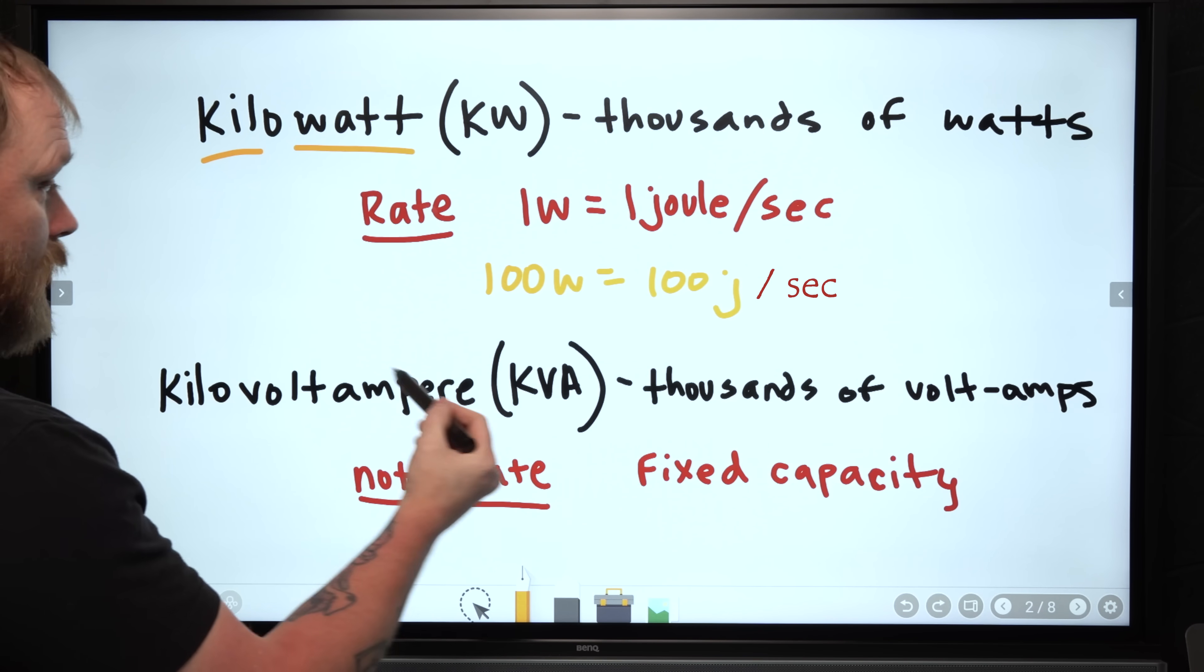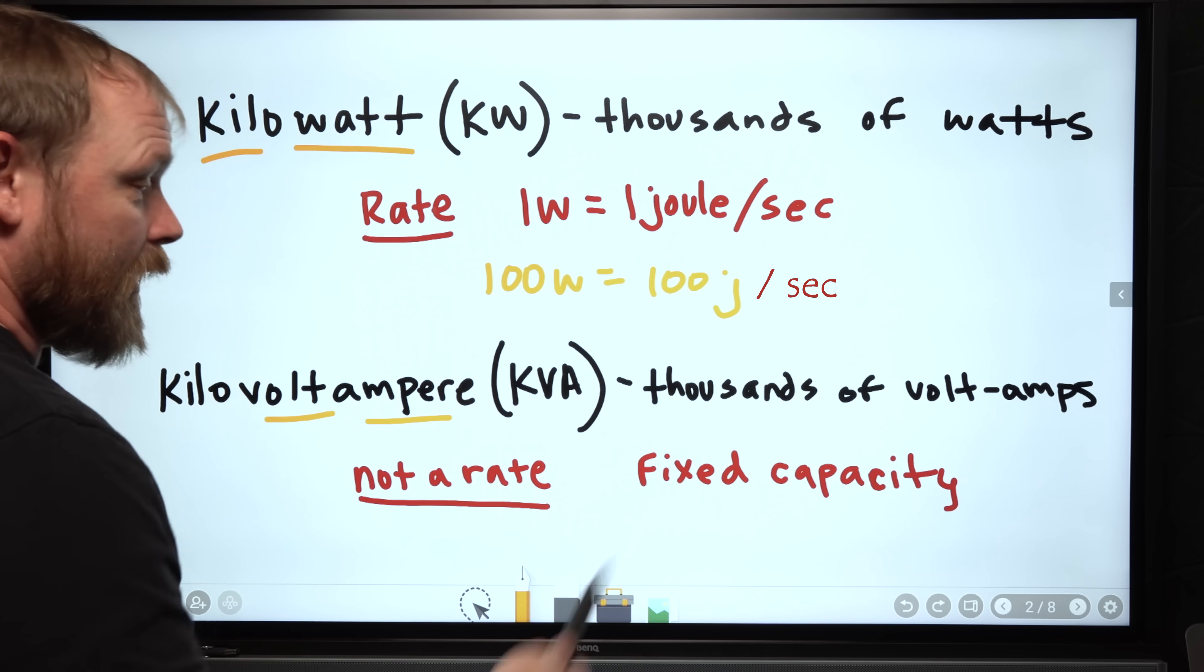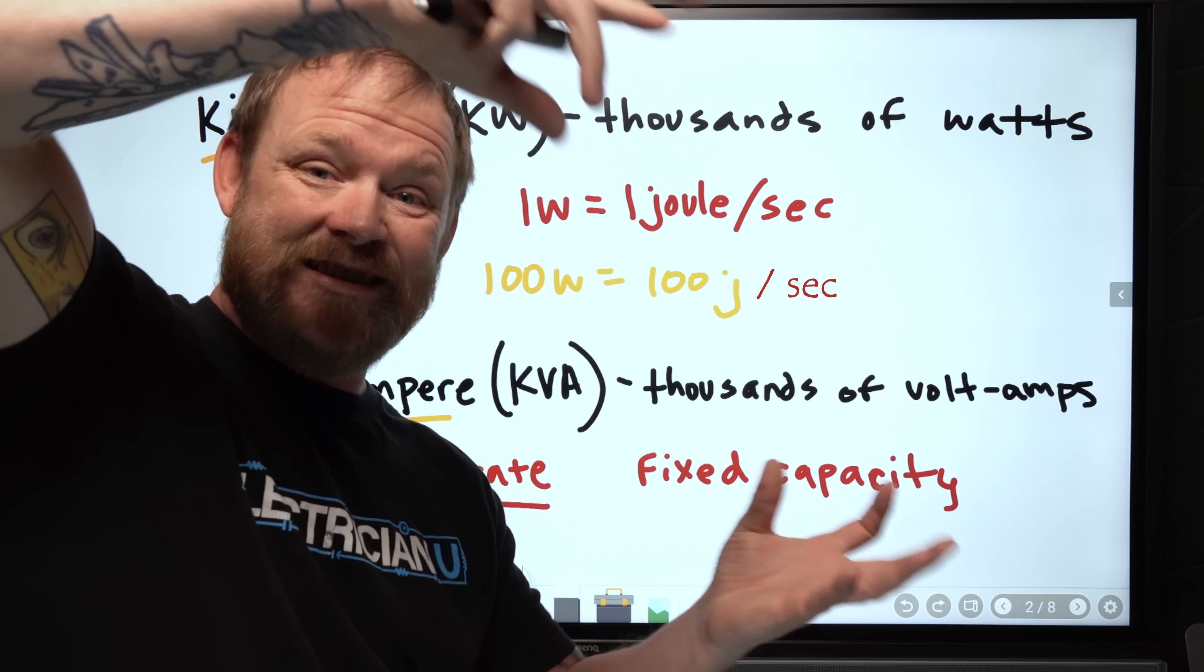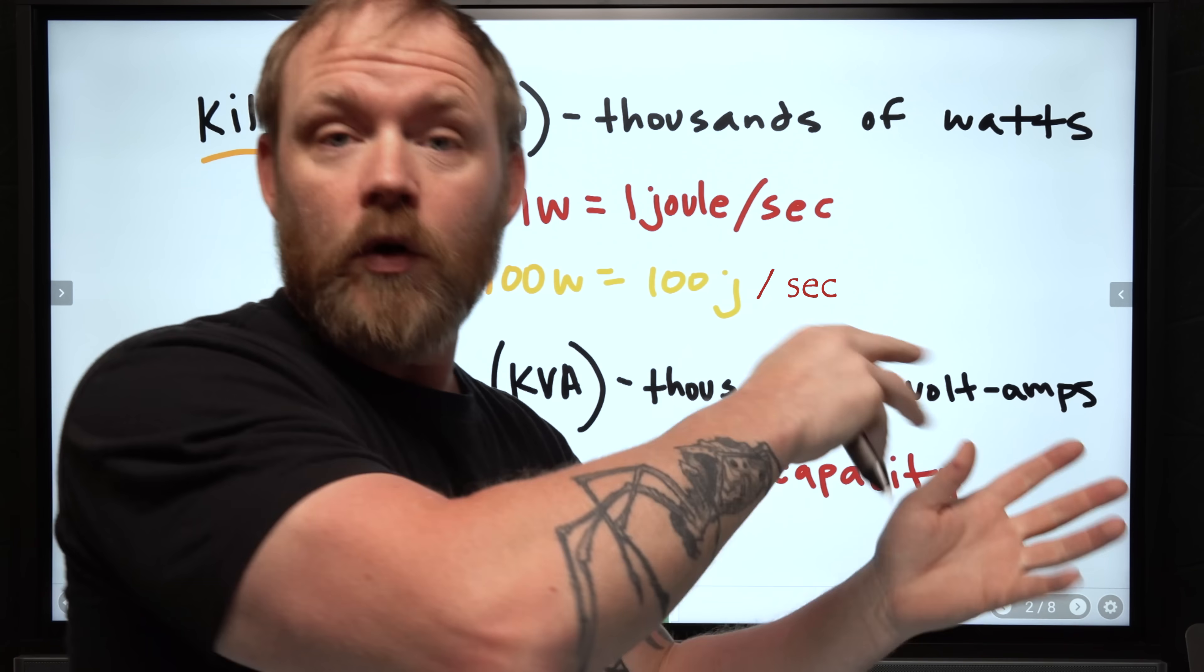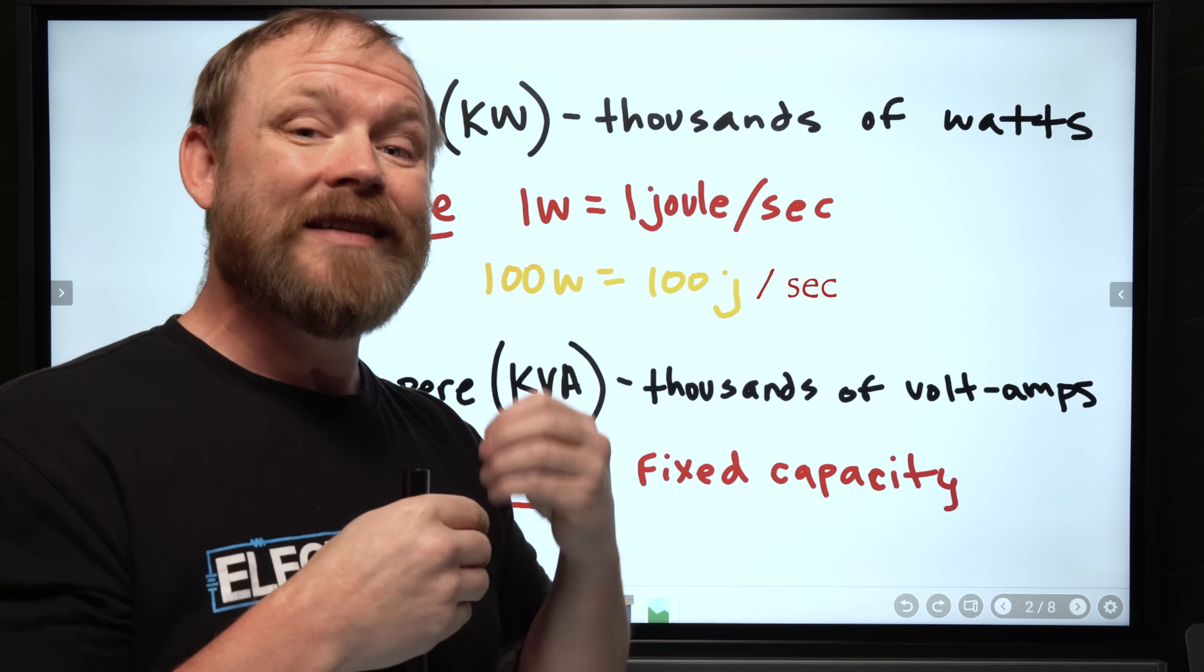When we talk about a kilovolt amp, KVA volt amp, volts times amps is a volt amp. We're talking about thousands of volt amps, and it's not a rate this time. It is a fixed capacity. When you talk about a VA, we're talking about how much fixed capacity does this system have to supply current flow, to supply a certain voltage, to be able to transfer energy to a load. A lot of times when you're talking about KVA, we're talking about the supply side. When we're talking about KW, we're talking about the actual load and what it's consuming. Storage capacity available and consumption.